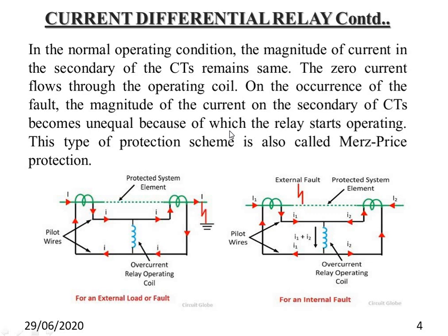If the fault occurs beyond this protection zone, then this differential relay will not work, and this kind of fault is called a through fault. So for an internal fault only, the differential relay will work. For a through fault or external fault, the differential relay will not work.